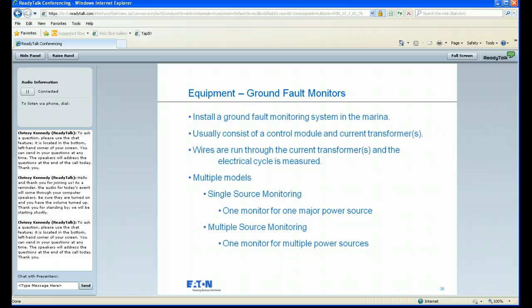Ground fault monitoring systems. You can install a ground fault monitoring system pretty much anywhere in the marina. It can be done on new installations and also most existing installations. It usually consists of a control module that can be adjusted to certain leakage levels, and we'll show you what the current transformers are and how they work here in a minute. But basically, you've got wires that are running through these donut-like objects that are measuring the electrical cycle that's present within a circuit.